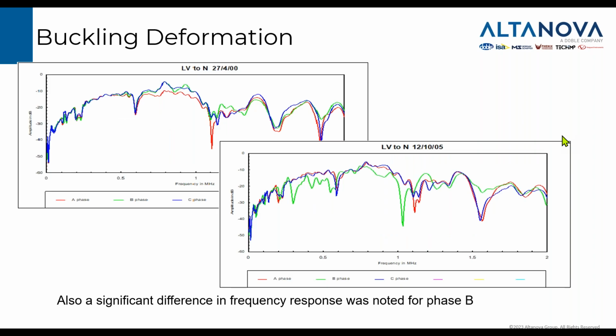We also had SFRA results, which showed us this. This is 2000, when the reference results came from. And this is 2005, when we tested it, when it was decided it would be subject to investigation. If you look carefully, you will see that B phase here differs from the other traces much more than here. Here it is actually quite good, up to some area above 1 megahertz, when traces naturally start to deviate slightly. In this case, the middle phase trace differed from the previous one strongly.